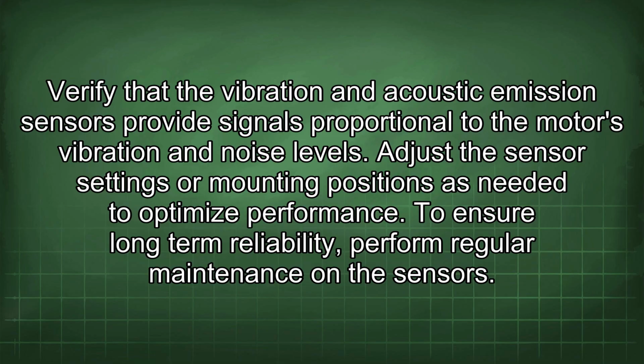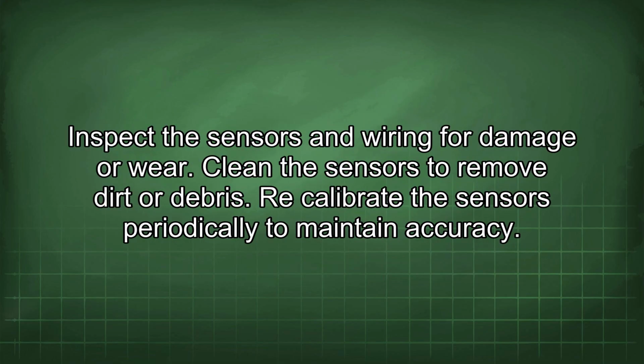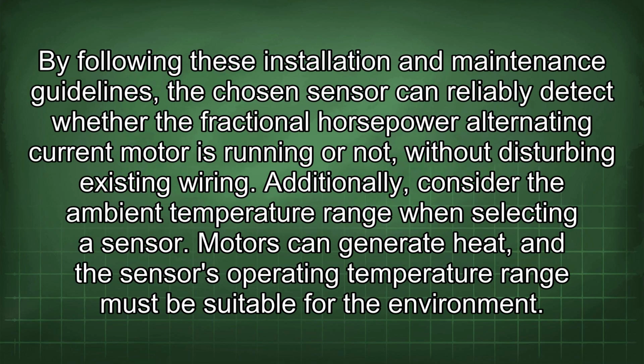To ensure long-term reliability, perform regular maintenance on the sensors. Inspect the sensors and wiring for damage or wear. Clean the sensors to remove dirt or debris. Recalibrate the sensors periodically to maintain accuracy. By following these installation and maintenance guidelines, the chosen sensor can reliably detect whether the fractional horsepower alternating current motor is running or not, without disturbing existing wiring.